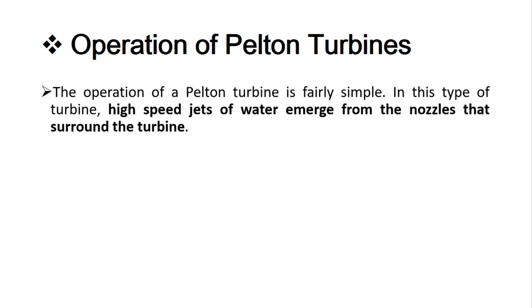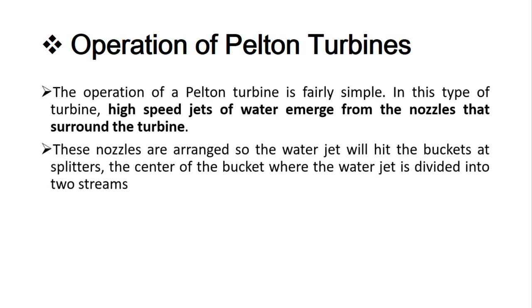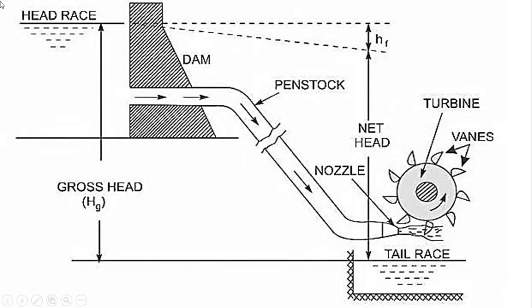The operation of a Pelton turbine is fairly simple. A high-speed jet of water emerges from a nozzle surrounding the turbine. These nozzles are arranged so that the water jet hits the bucket at the splitter — the center of the bucket — where the water jet is divided into two streams. Since the Pelton turbine is a high-head, low-discharge type of turbine, the head is always very high compared to other turbines.